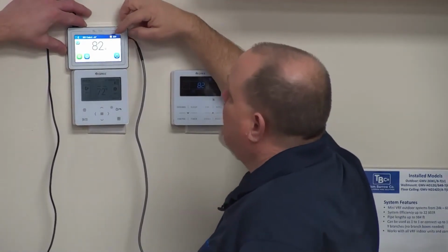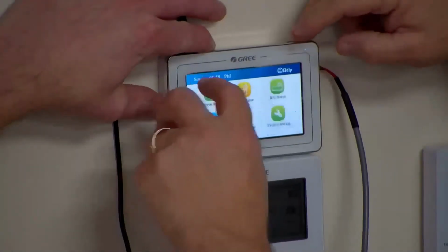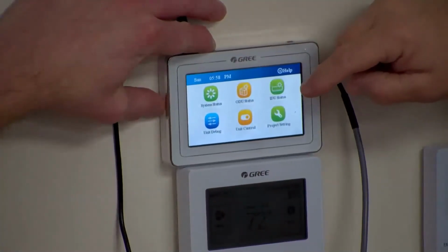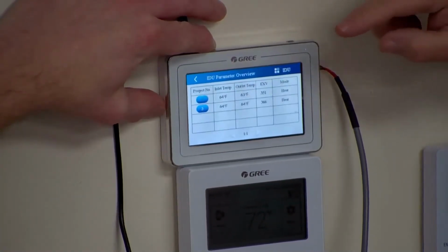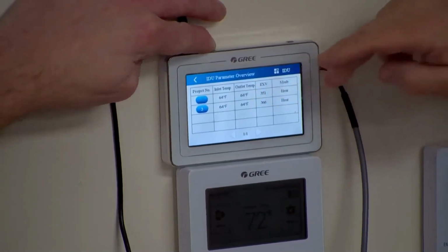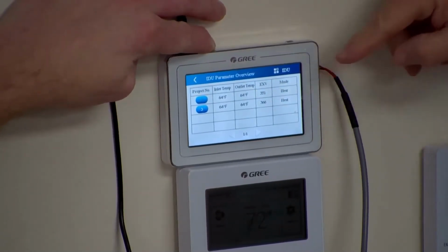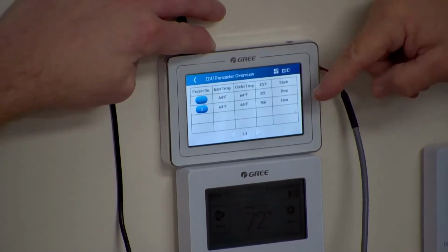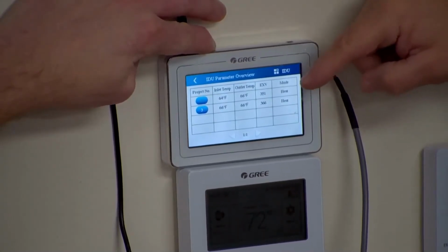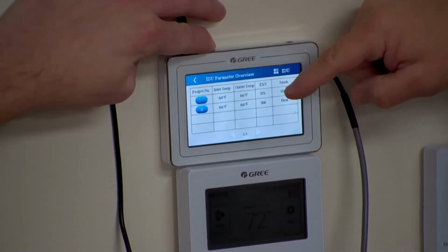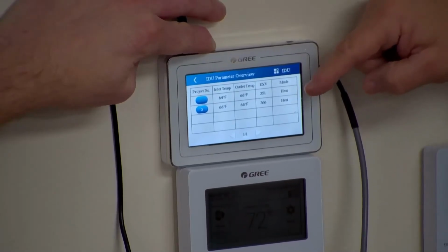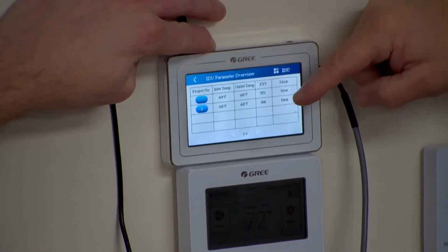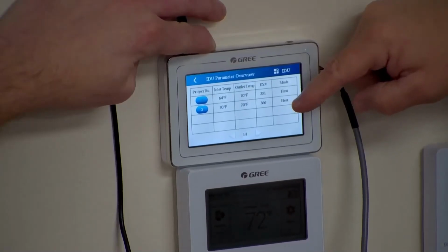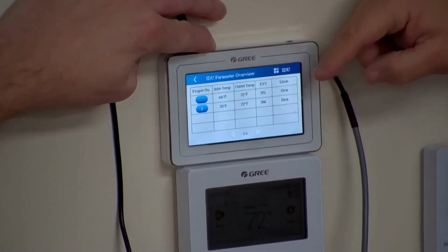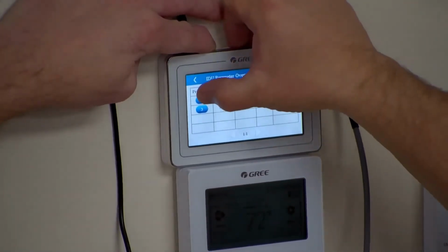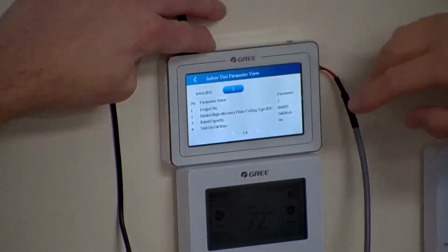All right, so now I can go back. I can go to indoor unit status. I can select both of them, and you can see right now, man, these things are cranked up because I've got such a high demand on it. Indoor number 2 has the EEV set at 351 steps. Indoor unit number 3 has it at 366 steps. Now I can hit that number 2 button and go specifically to that unit.